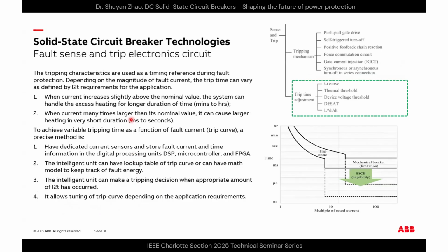So the tripping characteristic is used as a timing reference during fault protection. Depending on the magnitude of fault current, the trip time can vary as defined by the I squared T requirements for applications. When the current increases only slightly above the nominal value, the system can handle the excessive heating for a longer duration, minutes to hours, like here. But when the current is many times larger than its nominal value, it can cause larger heating in a very short duration, milliseconds to seconds, like here.